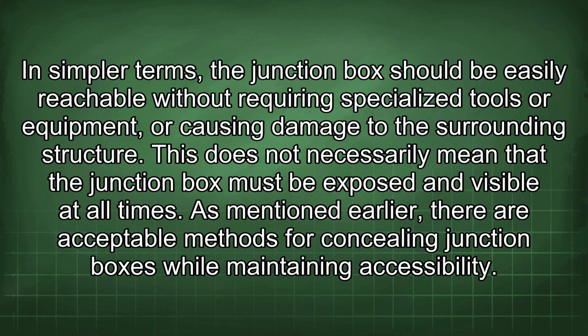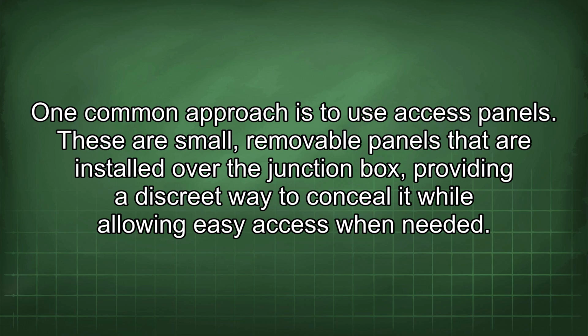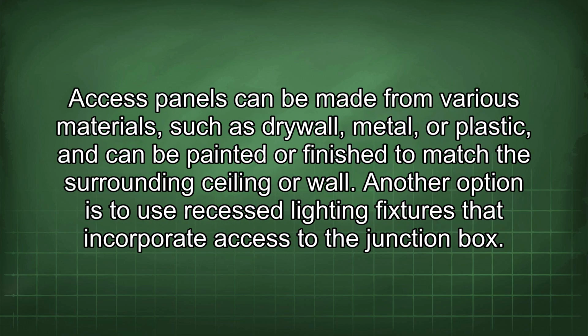As mentioned earlier, there are acceptable methods for concealing junction boxes while maintaining accessibility. One common approach is to use access panels. These are small, removable panels that are installed over the junction box, providing a discreet way to conceal it while allowing easy access when needed. Access panels can be made from various materials, such as drywall, metal, or plastic and can be painted or finished to match the surrounding ceiling or wall. Another option is to use recessed lighting fixtures that incorporate access to the junction box.